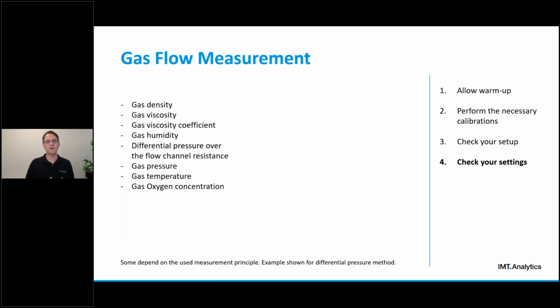Because of that, gas flow analyzers need to know many different parameters for the flow and volume calculations. The first three here on the list, gas density, viscosity, and viscosity coefficient, are defined by a gas type setting on your gas flow analyzer. So we need to tell the device or analyzer if we want to measure flow and volume of air, or for example, oxygen or CO2. There's a bunch of different gas types that we can select from, and this then defines the gas density and viscosity. You will find that setting on any gas flow analyzer.